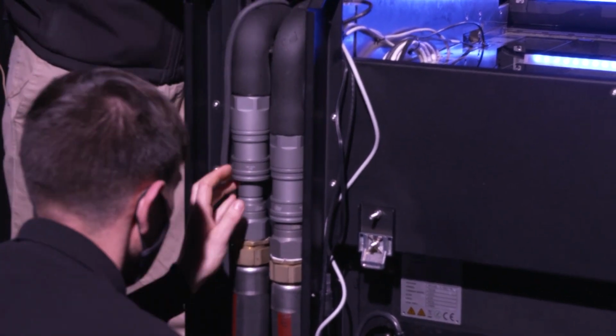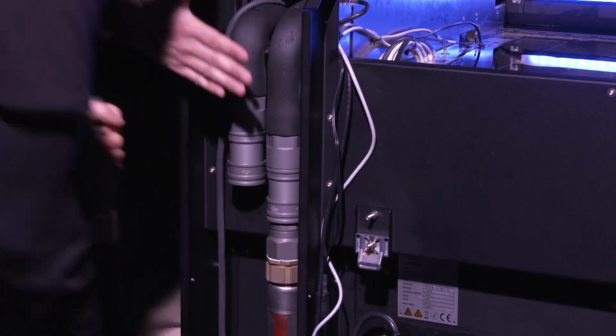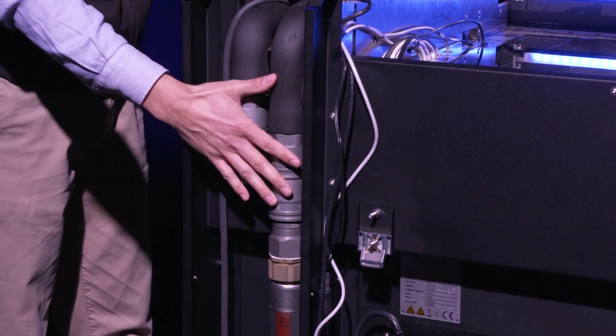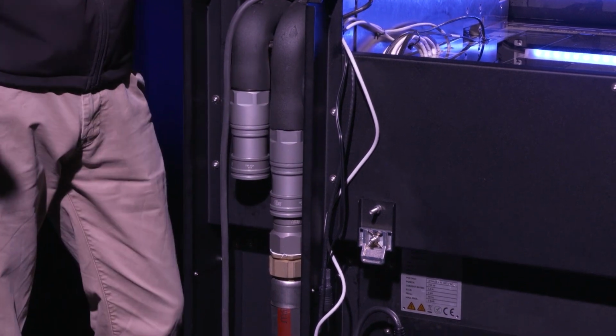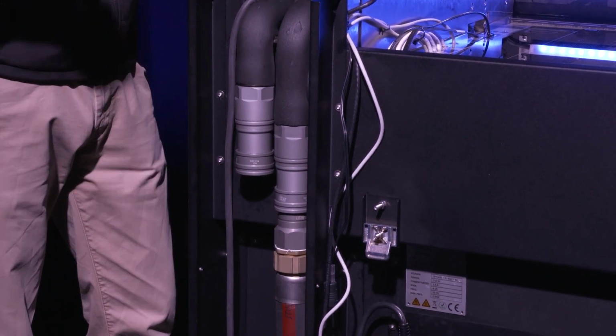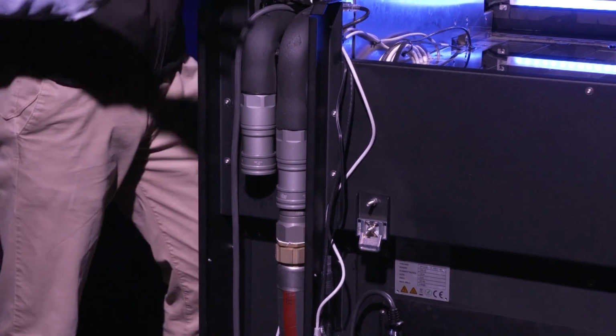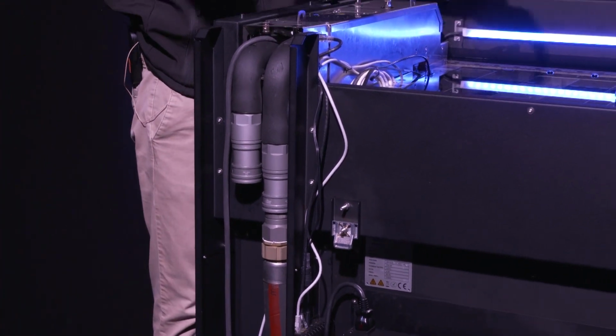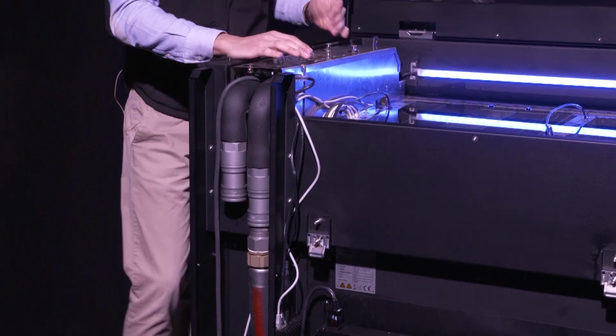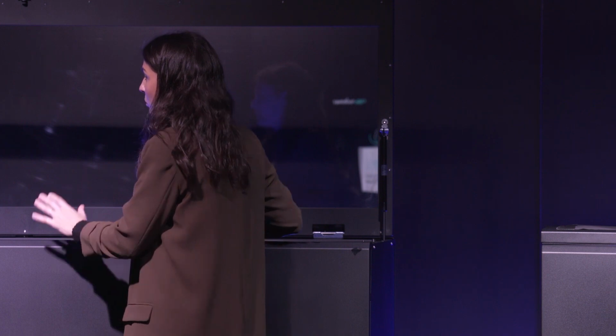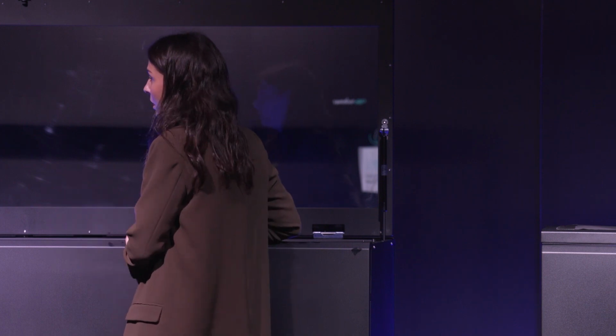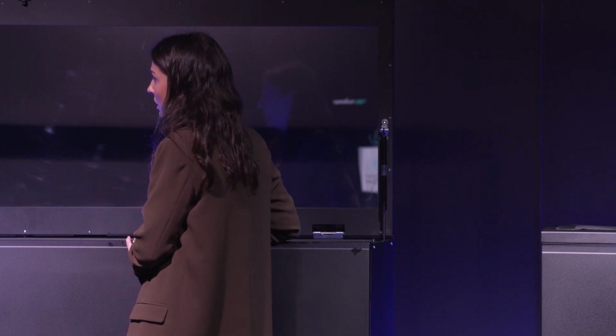This means that you can hot swap the CDU while the water is running. It's totally easy. You have a crane, like any typical data center crane. It can be manual or motorized, and you can replace any kind of server, but also you can replace the cooling. And I understand too that if you take out the CDU, the system will still work for an amount of time, just in case there are any kind of challenges.